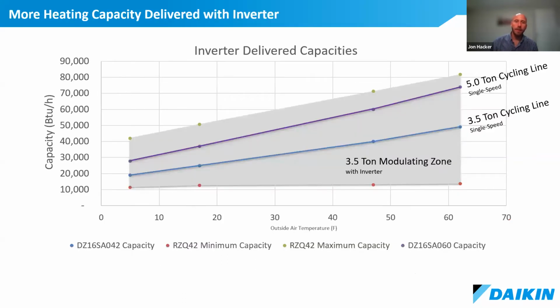Moving on a bit, we've gone from a cycling line, being able to deliver one capacity at one condition, to now being able to provide a broad array of capacities at that same condition. The other really enormous benefit to applying an inverter to a heat pump system is that it allows that same system to deliver more heat, specifically when it's cold out.